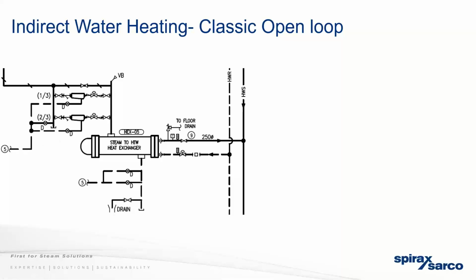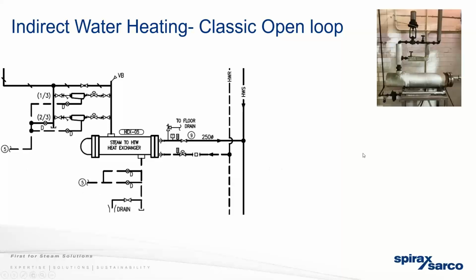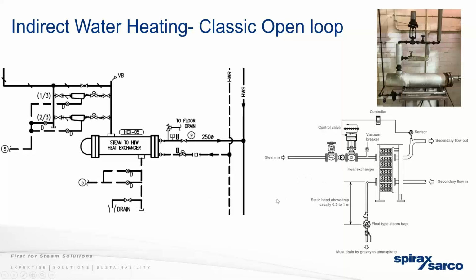So for indirect water heating, here's a picture, a P&ID, of a classic open loop system where we have a steam to hot water heat exchanger. This is typically what it would look like. You're going to have steam supply coming into a temperature control valve, going into a heat exchanger, and then a trap. And this trap is discharging up, which normally we wouldn't recommend. It would normally go to a gravity drain. This also could be a plate and frame heat exchanger. Similarly, you're going to have plant steam coming in, temperature control valve, heat exchanger, trap, and then gravity drain.